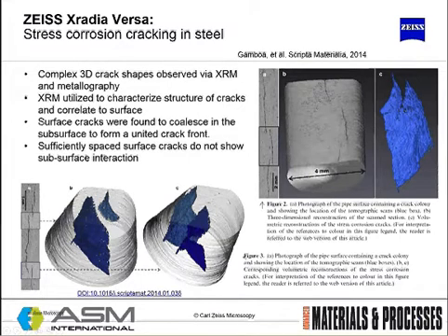And in this case, you can see that the surface appears to have maybe 3 cracks, but actually beneath the surface, they coalesce into a single large crack. So it vastly increases your ability to rapidly understand a crack non-destructively.